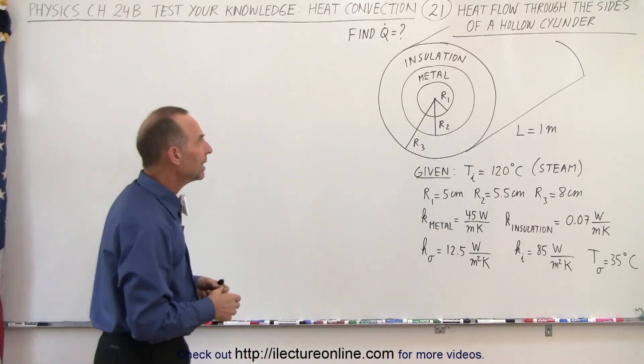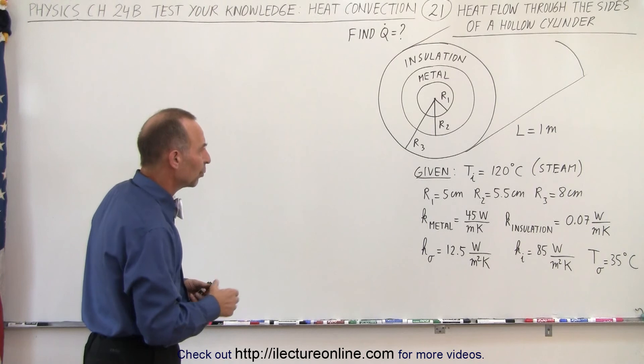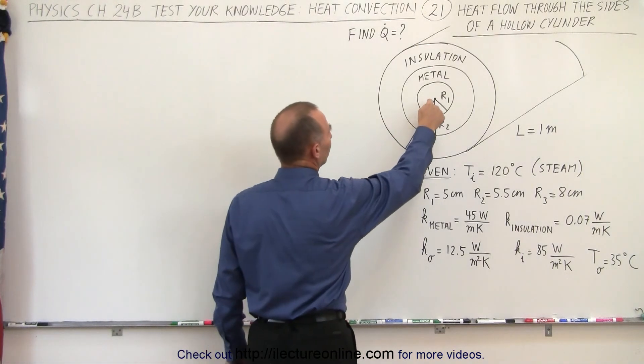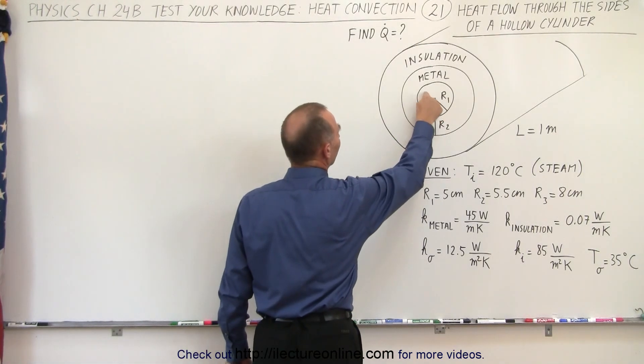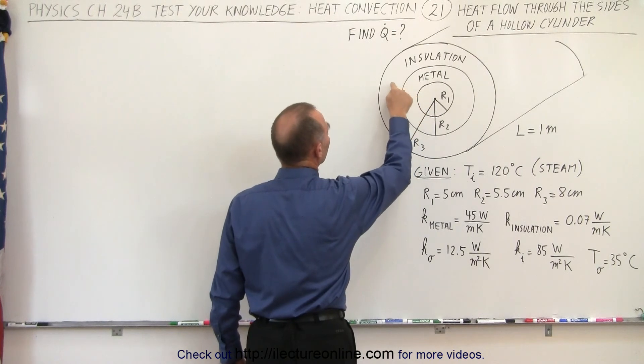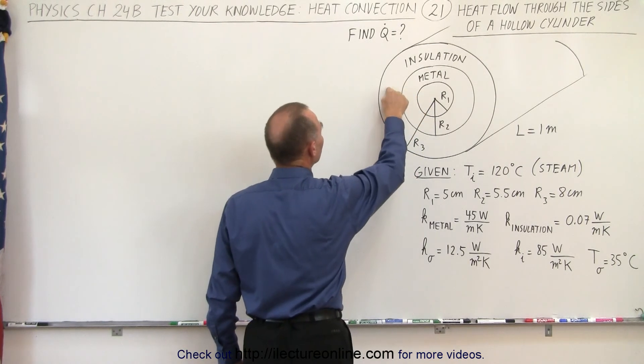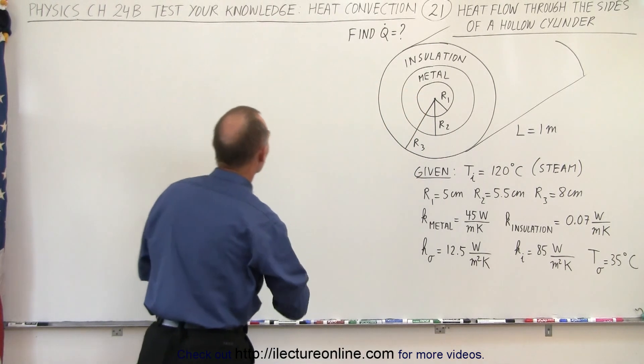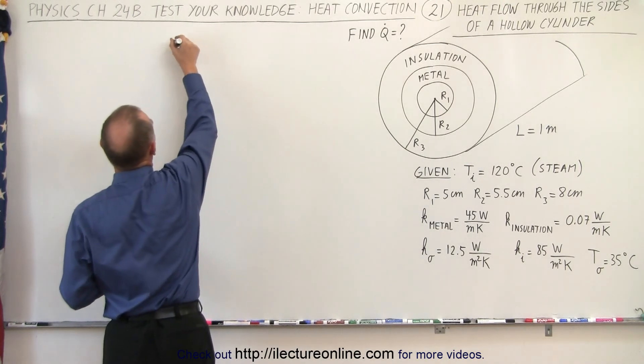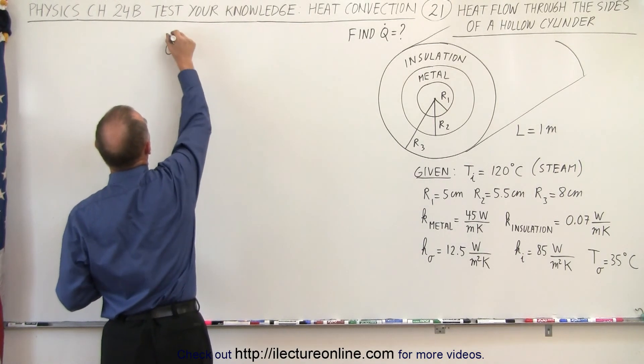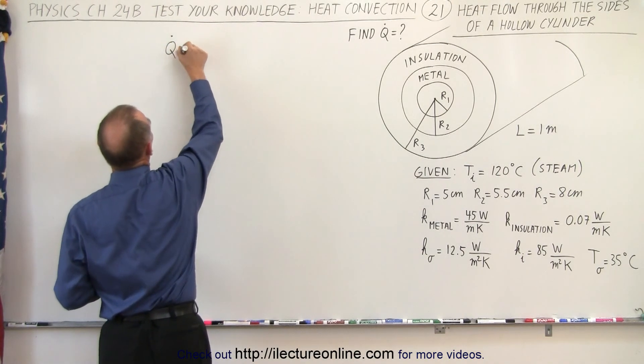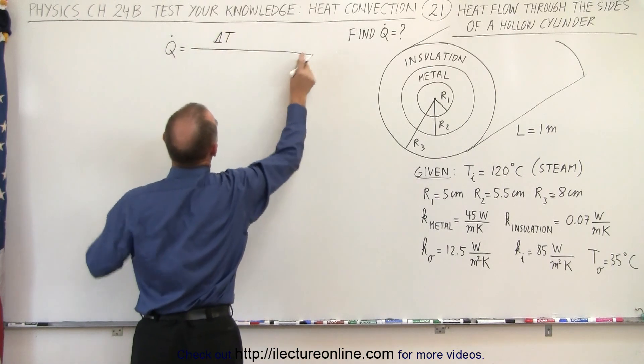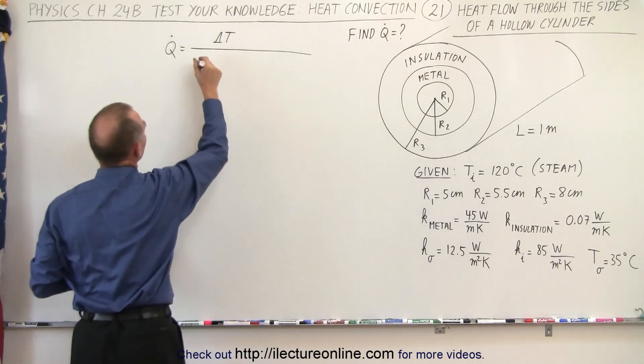So how do we calculate the heat transmission? Well, we have four things we need to consider: the transmission from the inside to the metal, through the metal, through the insulation, and from the insulation to the air outside. So our equation will look something like this — Q-dot is going to be equal to the difference in temperature divided by four terms.